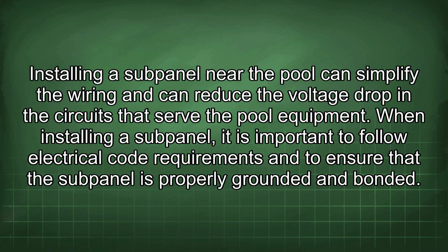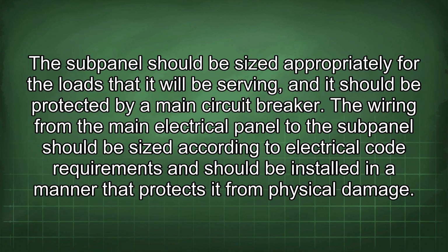When installing a subpanel, it is important to follow electrical code requirements and to ensure that the subpanel is properly grounded and bonded. The subpanel should be sized appropriately for the loads that it will be serving, and it should be protected by a main circuit breaker. The wiring from the main electrical panel to the subpanel should be sized according to electrical code requirements and should be installed in a manner that protects it from physical damage.